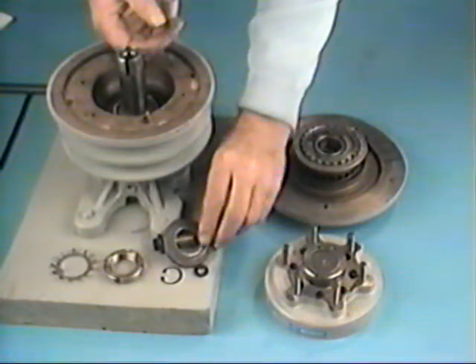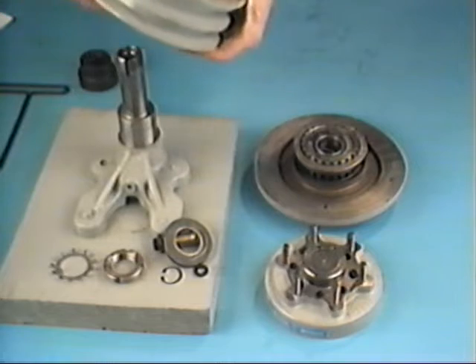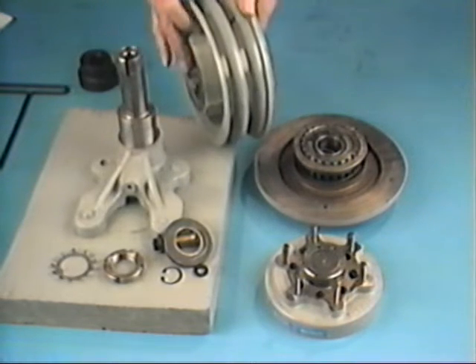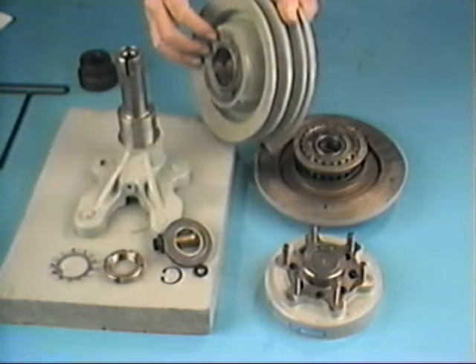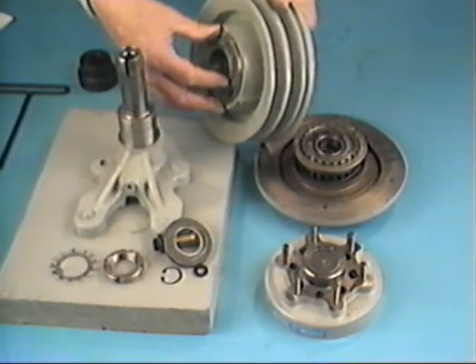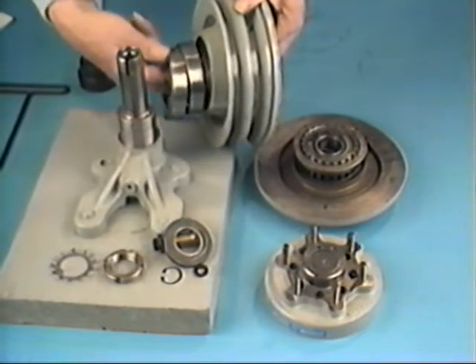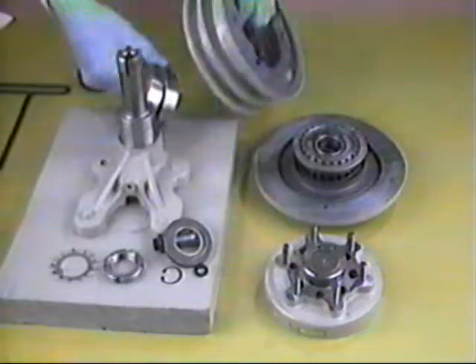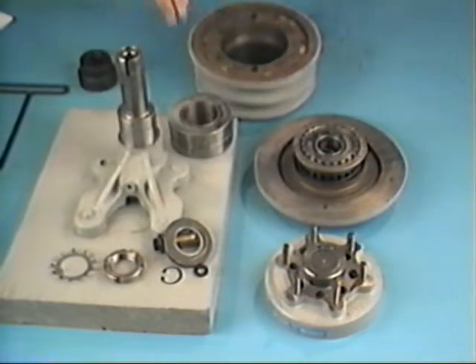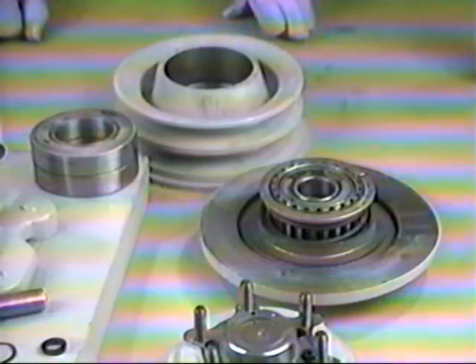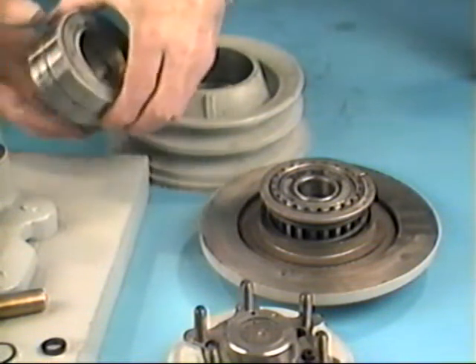Now remove the journal spacer from the shaft and slide the pulley assembly off the shaft. It is absolutely essential to replace all worn parts during this overhaul procedure. Remove pulley bearings by pressing them out towards the back of the pulley. Before replacing the bearing with Horton parts, be sure that the inner seals have been removed.